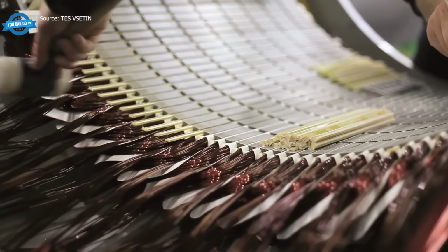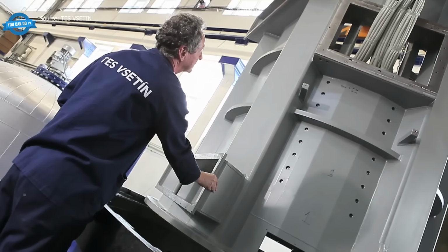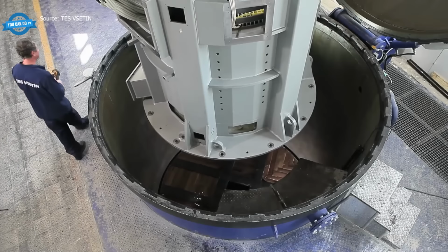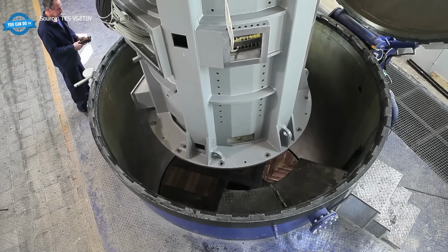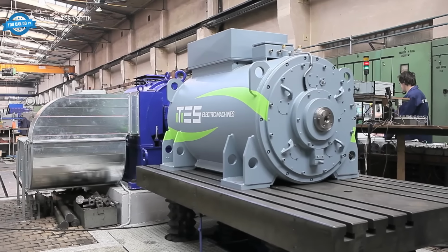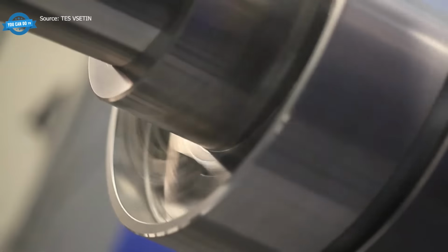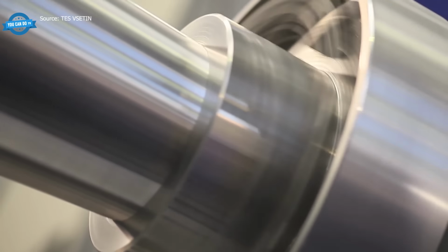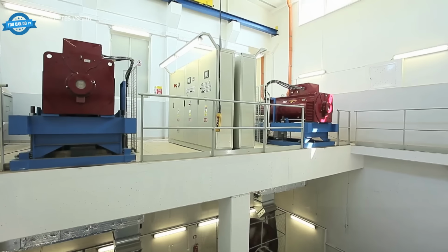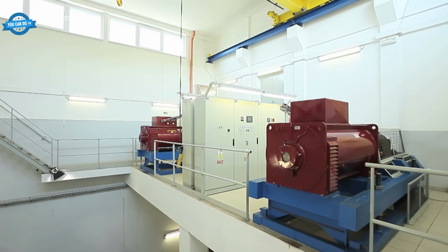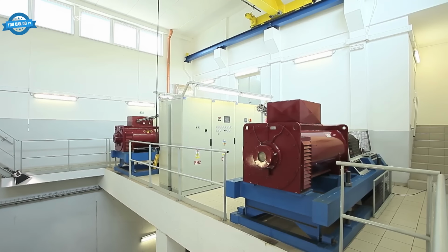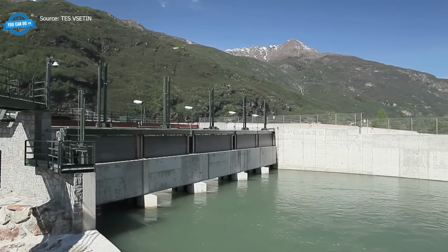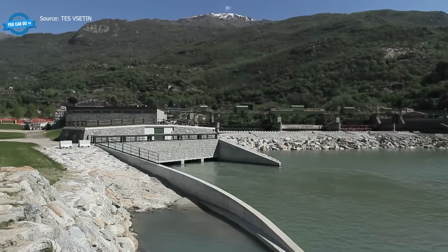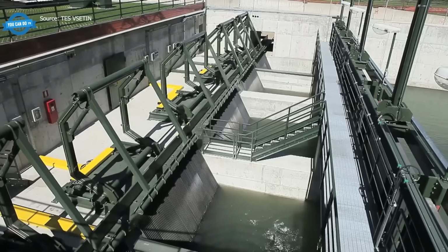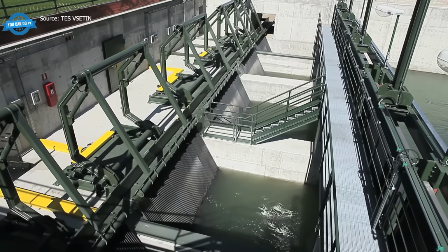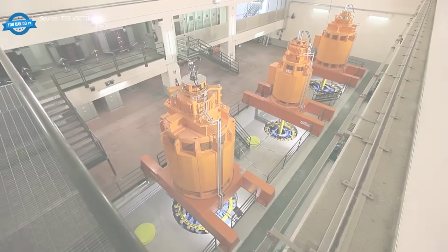The rotor is assembled separately, balanced dynamically on a dedicated machine to eliminate vibration at operating speed, and then inserted into the completed stator with the clearance between rotor and stator bore held to a fraction of a millimeter. After winding, the entire stator assembly enters a vacuum pressure impregnation chamber. Resin is introduced under vacuum and then pressure forced into every gap between conductors and between conductors and the core, eliminating voids that would otherwise trap moisture or allow vibration-induced movement. The assembly is then cured in an oven. Every finished machine is tested on a load bank before leaving the factory. Voltage, current, insulation resistance, temperature rise, and vibration level are all verified against specification.